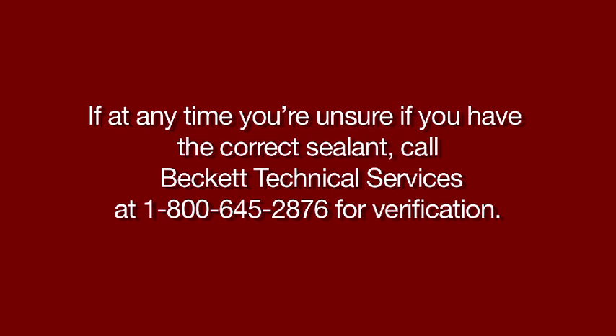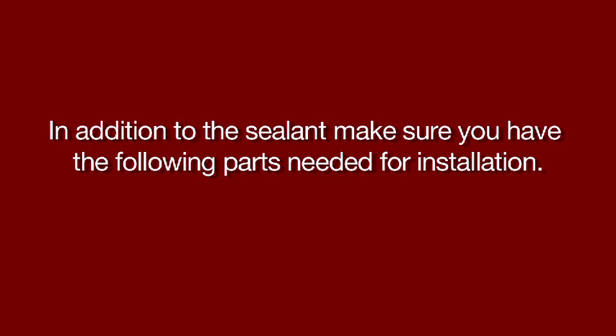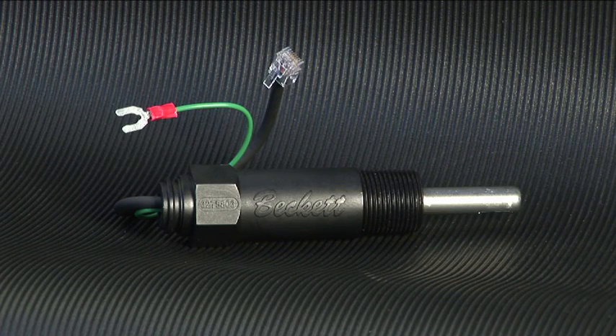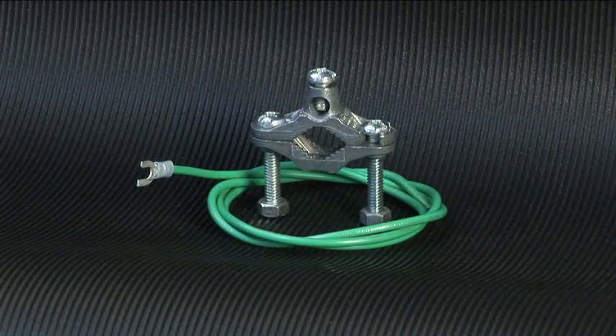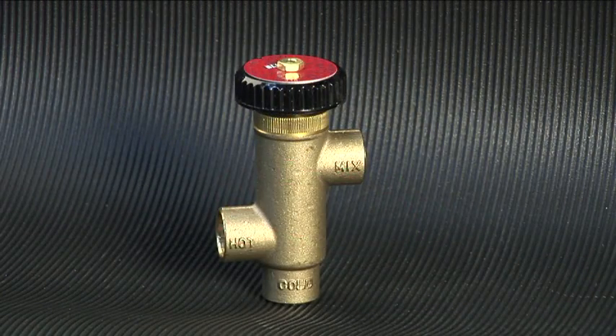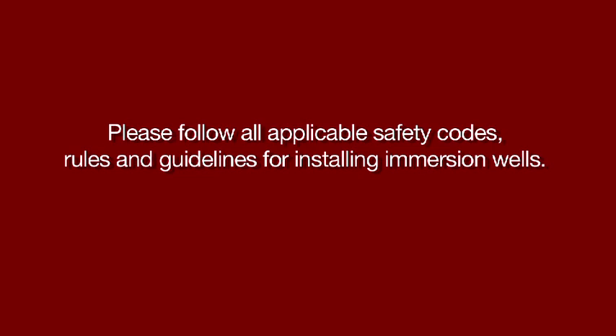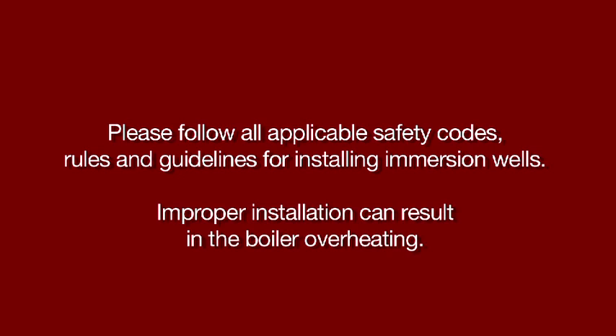If at any time you're unsure if you have the correct sealant, call Beckett Technical Services at 1-800-645-2876 for verification. In addition to the sealant, make sure you have the following parts needed for installation. These include the 2-in-1 replaceable sensor, Beckett thermowell, pipe clamp, and 36-inch green wire for sensor grounding. Also, make sure that the plumbing for domestic hot water has anti-scald valve protection. Please follow all applicable safety codes, rules, and guidelines for installing immersion wells. Improper installation can result in the boiler overheating.